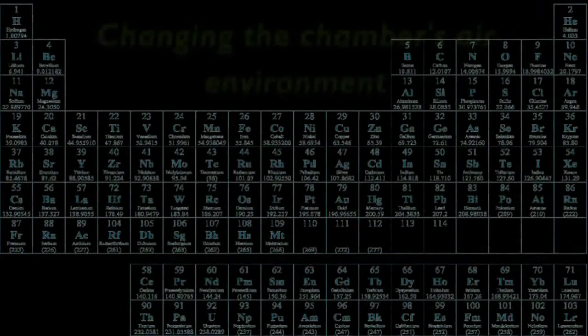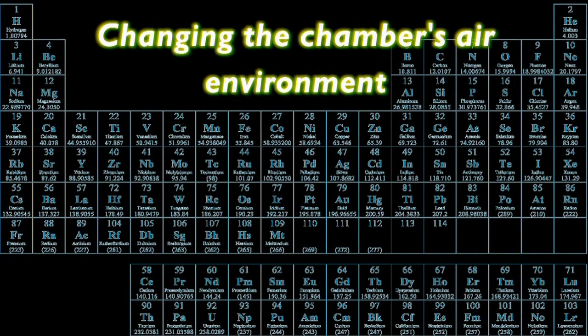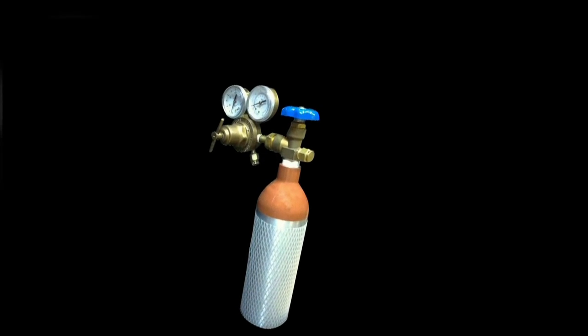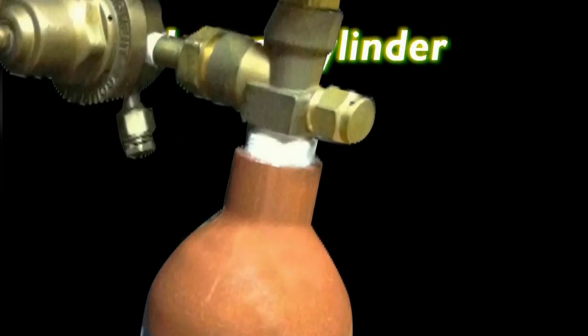Integrated ability of changing the chamber's air environment to helium enables detection of light elements starting from fluorine. Detachable small-sized helium cylinder to support light elements analysis in the field.